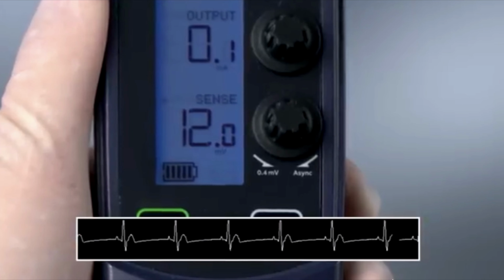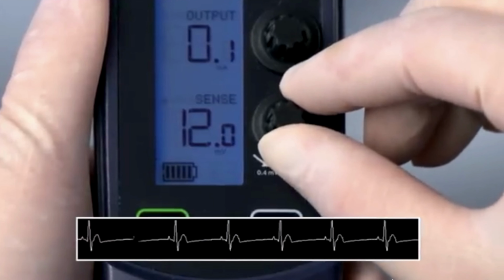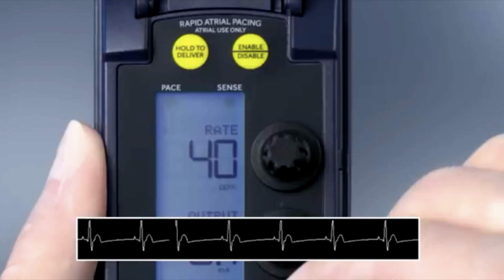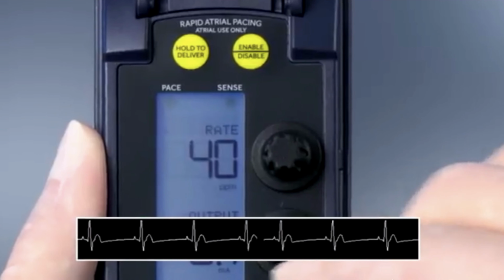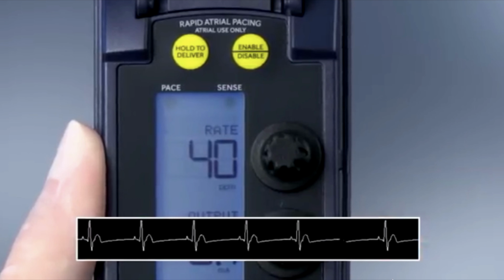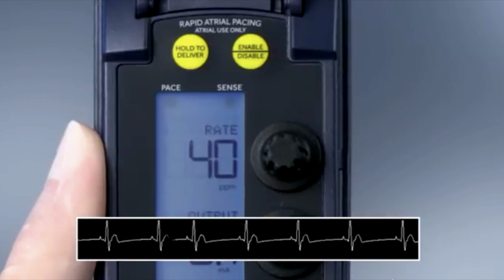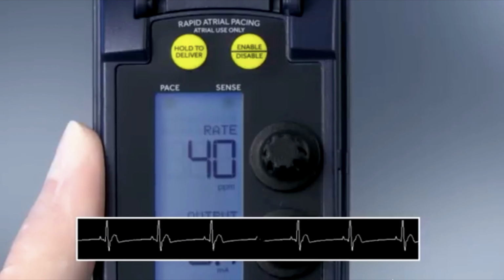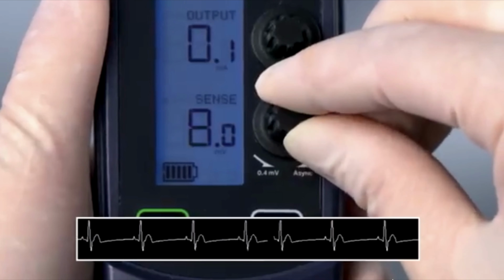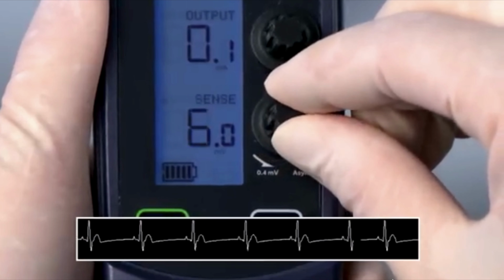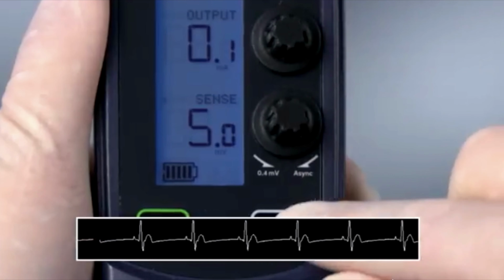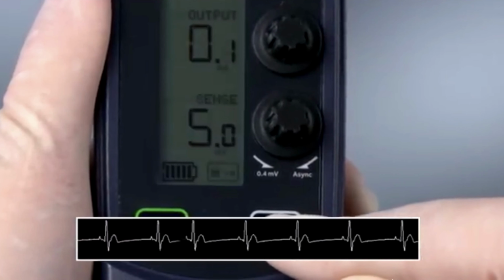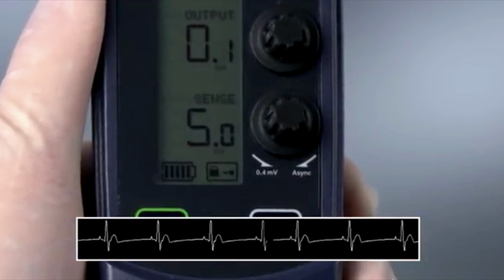Next, increase the sensitivity by slowly turning the dial counterclockwise, which decreases the millivolt value, until the sense indicator starts flashing. The pace indicator then stops flashing. This is the ventricular sensing threshold. Set the sensitivity dial to half or less of the threshold value. This setting provides at least a 2 to 1 safety margin for sensing.